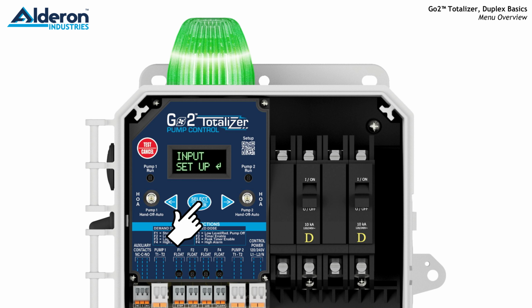Under Input Setup, you can make changes to the following parameters. Under Lag Float parameter, you can change the function to lag an alarm or lag pump start only with no alarm. Under High Alarm Float parameter, you can choose alarm only or alarm and start the pump. Under Float Errors parameter, you can choose to enable, where the alarm is activated if the floats are out of sequence, or you can disable to eliminate this feature.